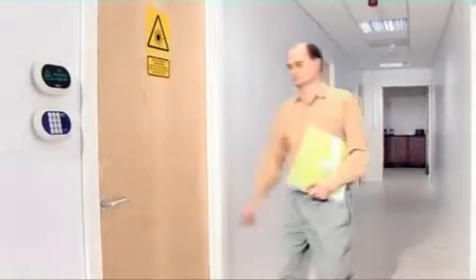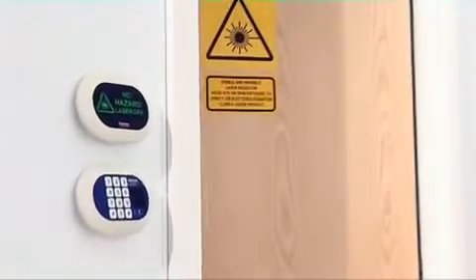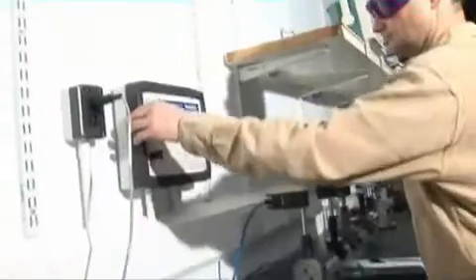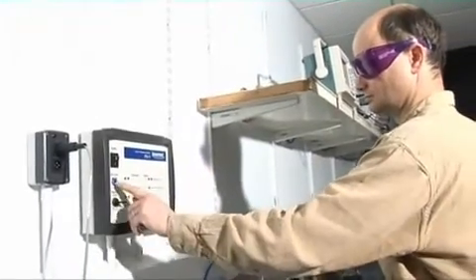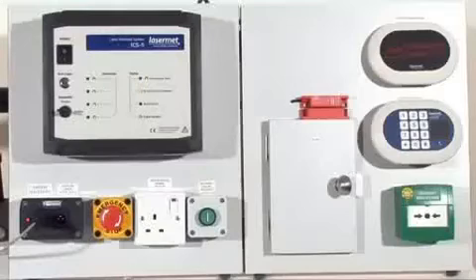What we have demonstrated so far is the standard, non-locking laser interlock system. However, for laser operating theatres, laser lab experiments with a long duration, or other laser processes which would be costly or undesirable to interrupt, we recommend configuring the ICS-5 as a locking interlock system.